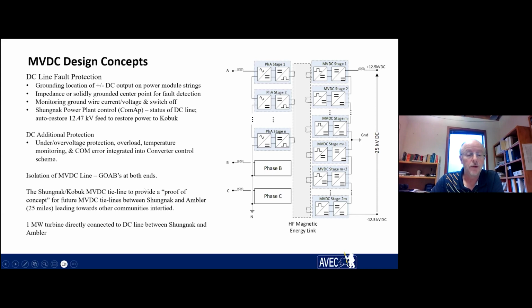So basically, this DC line is a proof of concept for future lines between Shungnak and Ambler, as Sunny was mentioning. On the converter side, they can have different ports on DC. So you could have one converter that would provide a tie to Kobuk. You could have another tie through a different port on that same converter that would head towards Ambler. In this case, we'd probably have separate ones because the first one's funded. The Ambler to Shungnak one is just being looked at now and not funded.